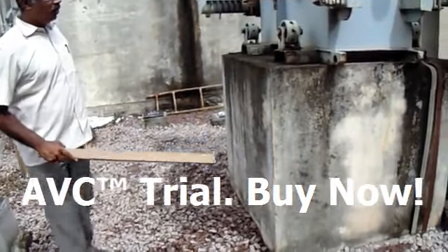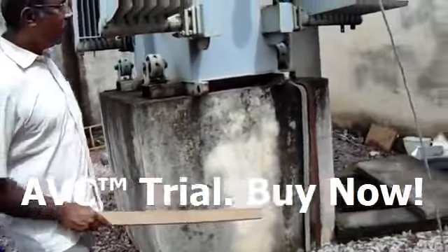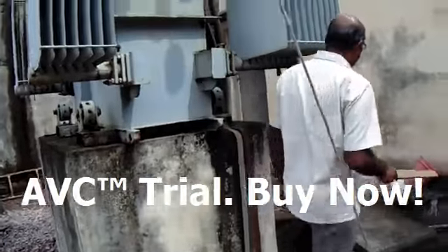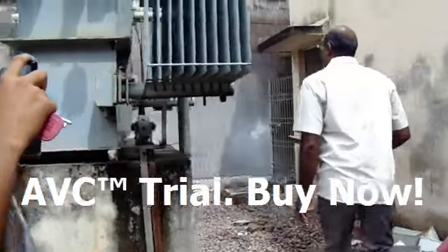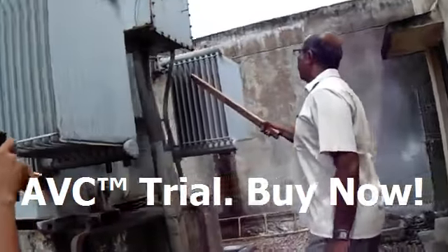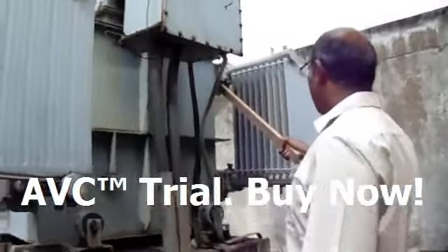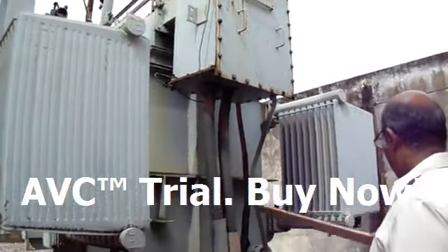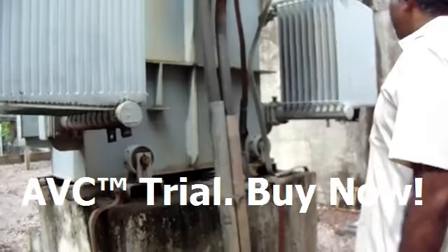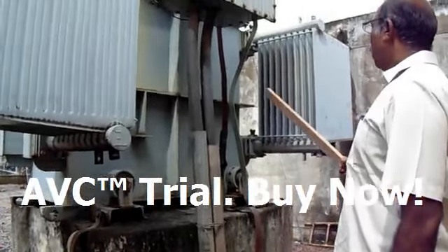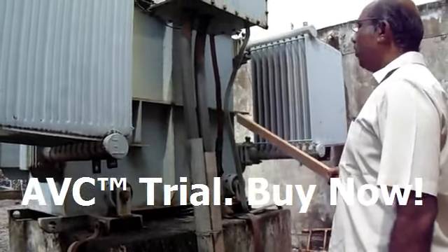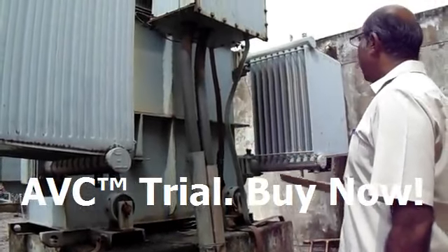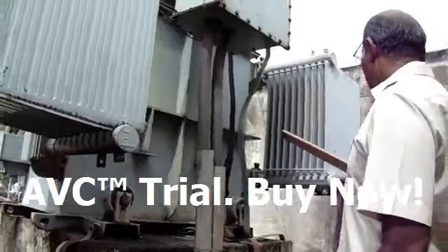One important feature of the transformer is that on the LT side, the neutral should be grounded. So we have grounded the neutral. It goes to the earthing pit. There are two important earthings: one is the neutral earthing, and the second is the body earth.